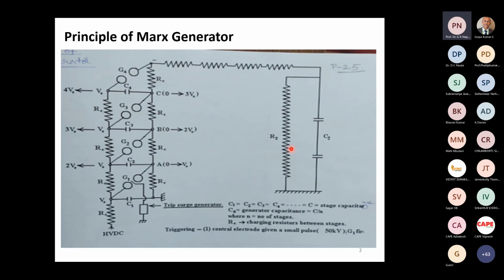What we do is we have got multiple stages. If there are n stages, each stage is charged to 1/n of the voltage, and when they are connected together by a triggering gap, you will see that they get added up to n times the stage voltage. That's how we get very high voltages. Typically, the highest stage voltage is 200 kV. So if there are 10 stages, you get 2 million volts, 200 into 10, 2000 kV. If we have 100 stages, we can get much higher, but they're not very practical. So this is the basic principle of the Marx generator.